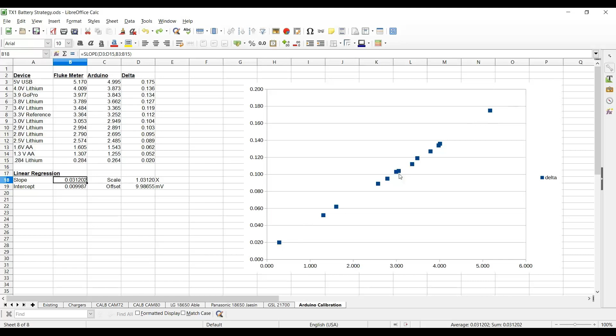So if we go back to the code, you'll see how I implemented putting this calibration line into the calculation. So I went back in the code and added a couple of constants. Scale is 1.0312, which represents the corrected slope of our line, and the offset is 0.009987, which reflects the offset of our line. Now, where we apply it is down here. After we calculate volts from the raw analog reading, I add the offset to the voltage, which is going to boost the whole line up by 9.9 millivolts. And then I multiply by the scale, which is going to bend the line up a tiny bit. And that's all we have to do.